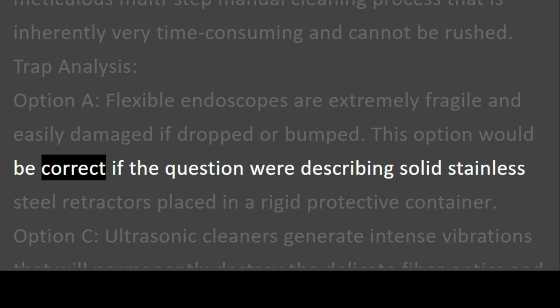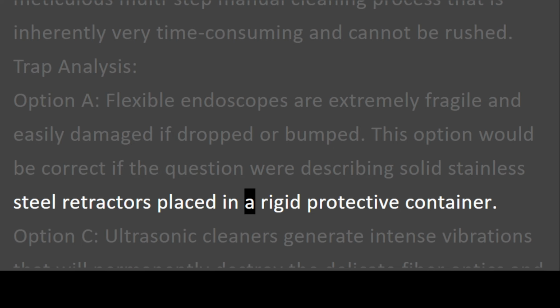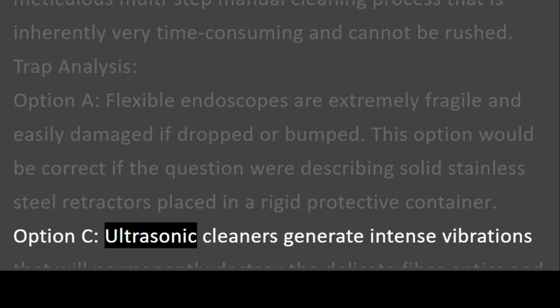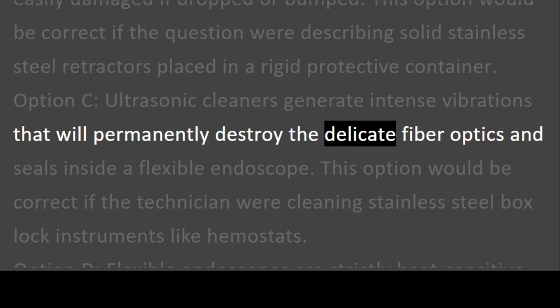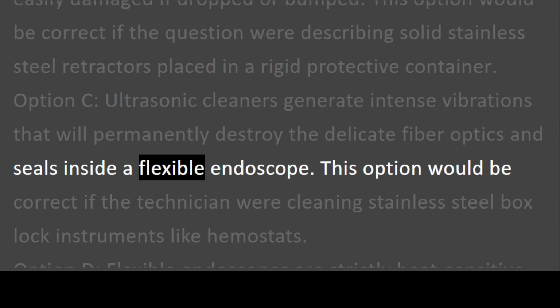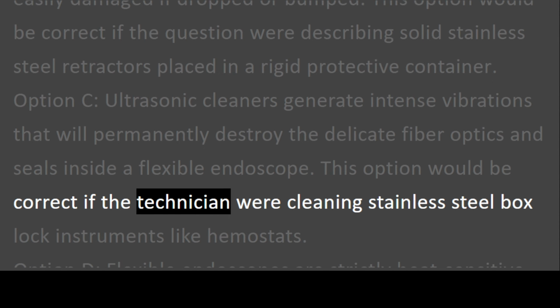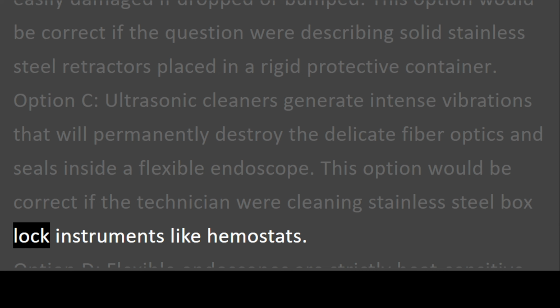This option would be correct if the question were describing solid stainless steel retractors placed in a rigid protective container. Option C. Ultrasonic cleaners generate intense vibrations that will permanently destroy the delicate fiber optics and seals inside a flexible endoscope. This option would be correct if the technician were cleaning stainless steel box lock instruments like hemostats.